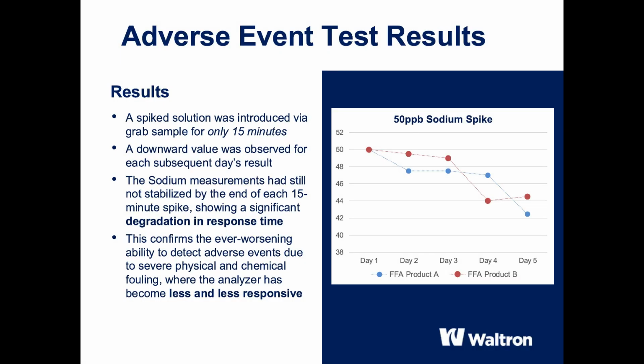After understanding the baseline drift, we wanted to know how the system would respond to a sudden contamination intrusion. The results of this breakthrough test are perhaps the most concerning of the entire study. We introduced a sample containing 50 ppb sodium for just 15 minutes.